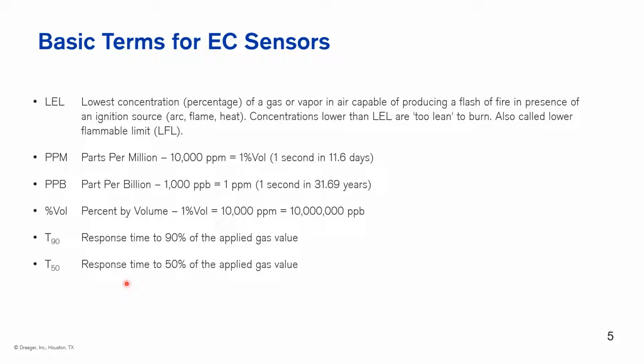So just to start off, a few basic terms that we use for EC sensors. Yes, at Dräger, we do use LEL for electrochemical sensors. We have a hydrogen sensor that is electrochemical that measures 0 to 4% by volume or 0 to 100% LEL. And we can couple that sensor with one of our infrared combustible sensors. Infrared doesn't do hydrogen, so this gives us a more complete range of combustibles when using an infrared sensor. So LEL, the lowest concentration of gas needed to have an explosive atmosphere. So with hydrogen, that's at 4% by volume, and that's the range of our electrochemical sensor for hydrogen.